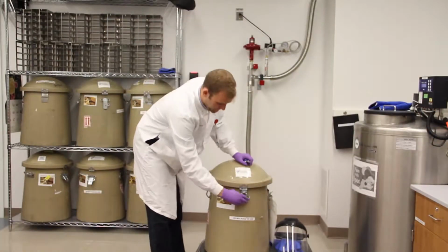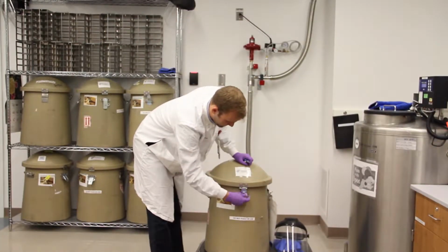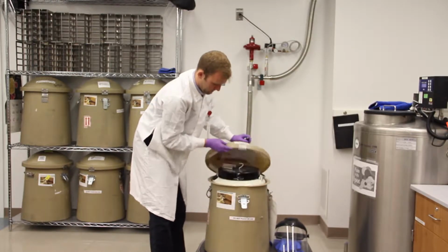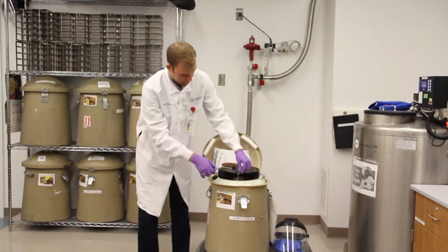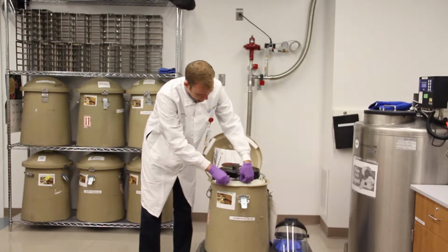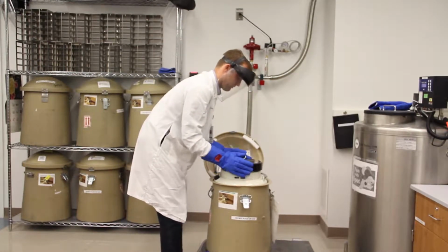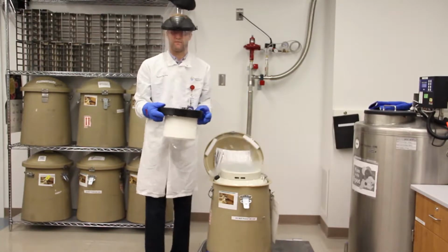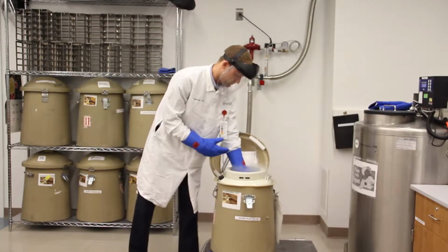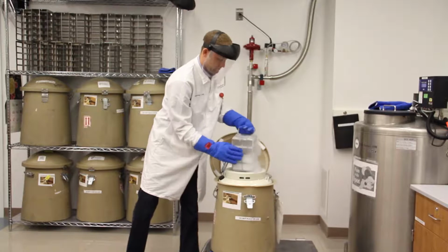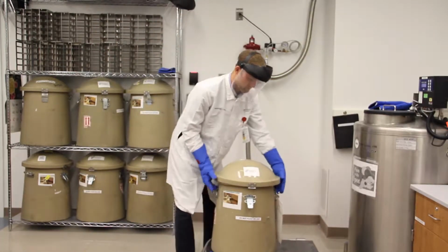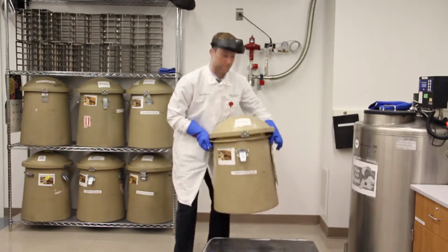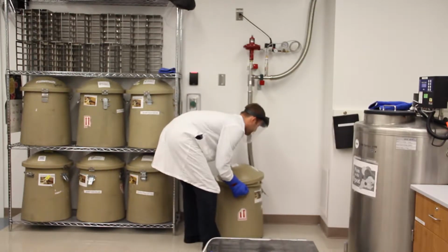To begin, lift the hood and use your cutting shears to remove the zip tie securing the black dewar lid. Lift the black lid by gripping the sides and set it aside. Please do not disrupt the data logger. Then remove the metal rack. This can be set aside until you are ready to ship specimens. You will fill the dewar with liquid nitrogen to the designated fill line.